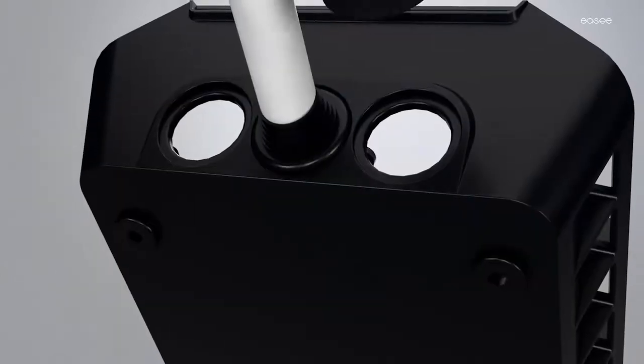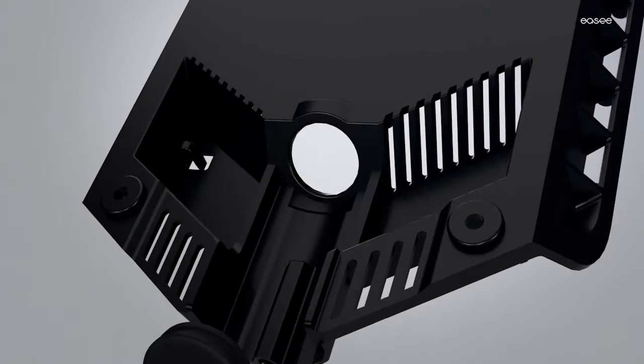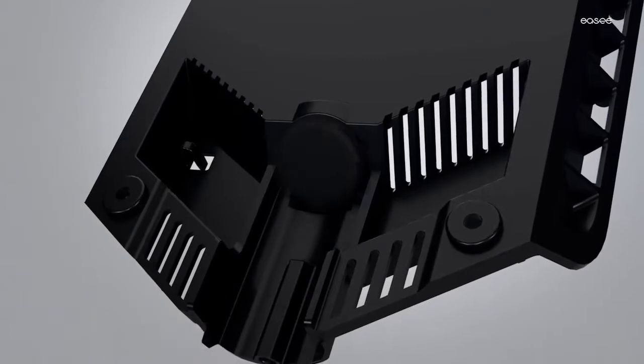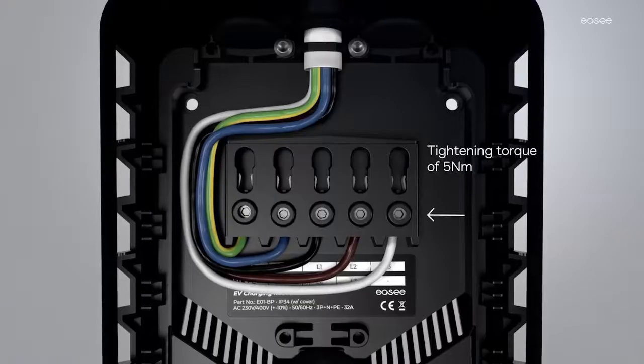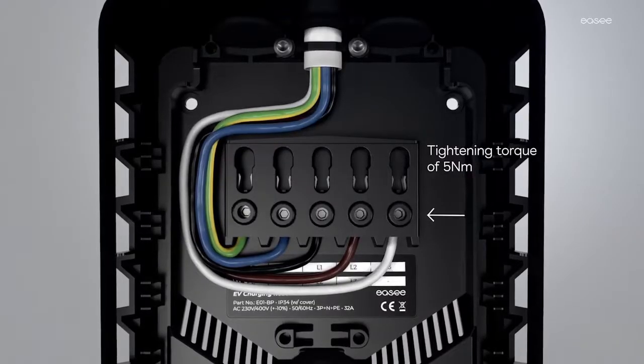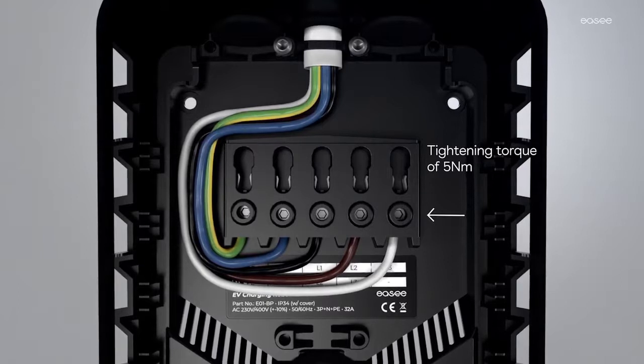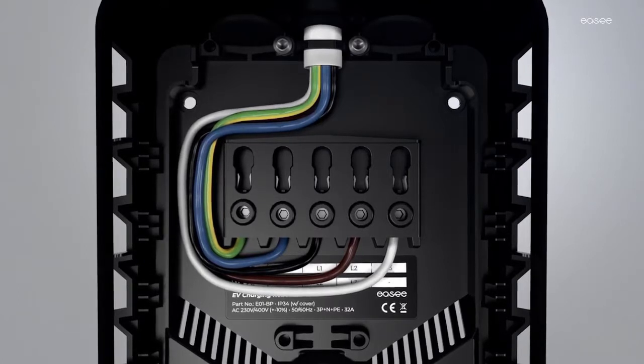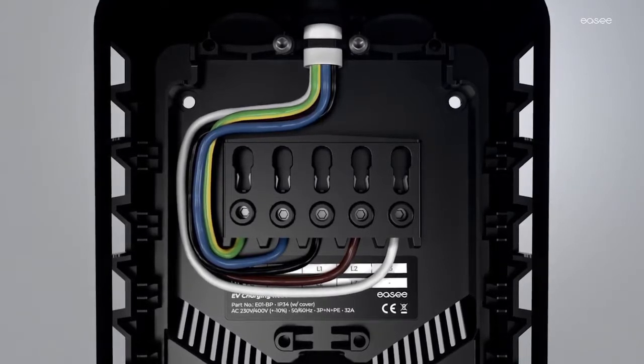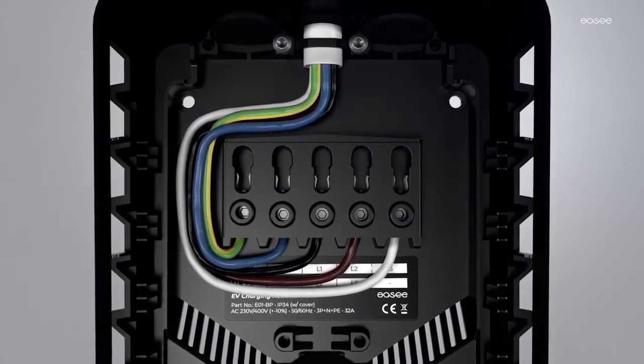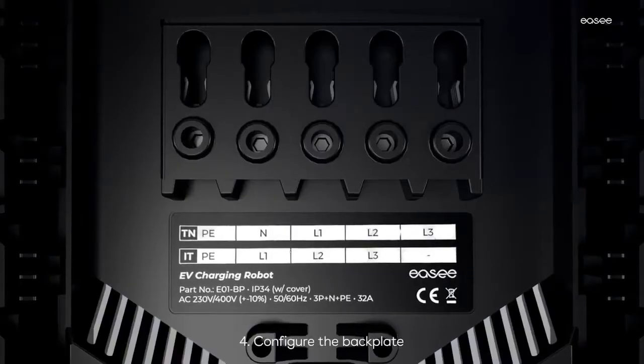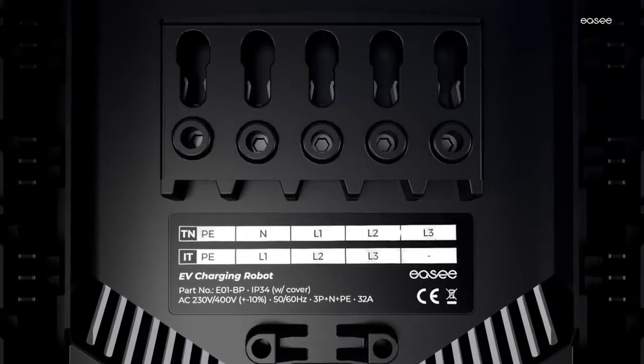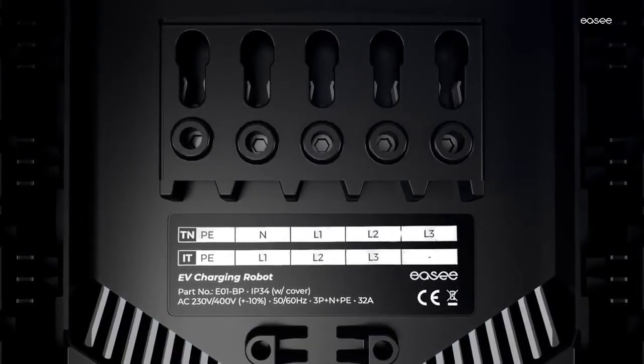Close all holes not used for cable entry with the blind sealing plugs. Tighten the screws with a torque of 5 Nm. Inspect all terminations before mounting the electronics. Follow these instructions to connect the backplate to different power grids.